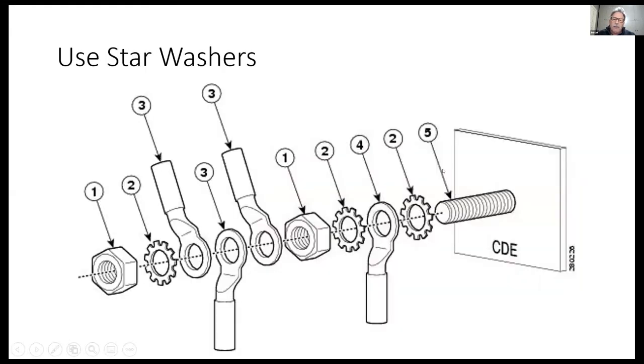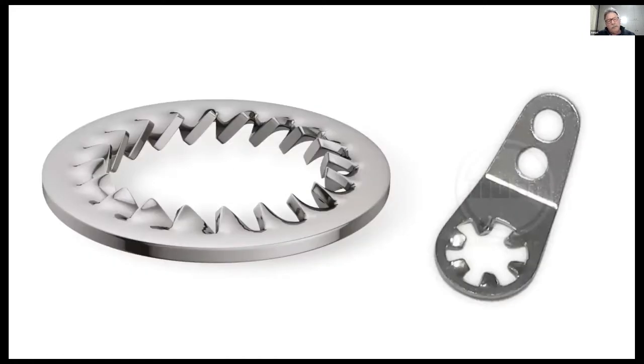The concept is you take a stud and put a washer on it, then a crimp connector with a wire in it, another washer, a nut, and you can stack them up. On the left-hand side you can put multiple terminals - you don't need a washer and nut between each one. But the key thing is to use a star washer, something that will cut through either the paint on the appliance or the metal panel, and also cut through the oxide layer on any connector and terminal.